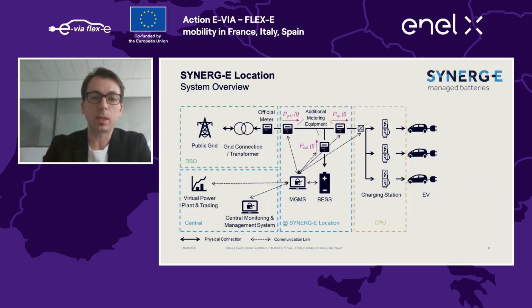Here you see what we deployed at the different locations. In the middle is the BESS, the battery energy storage system, connected to a microgrid management system which controls and steers the battery according to measured power flows at the location. We equipped the location with additional metering units to monitor every power flow, and this microgrid management system is connected to a central monitoring system and to virtual power plants to get direct controls from the different energy markets.